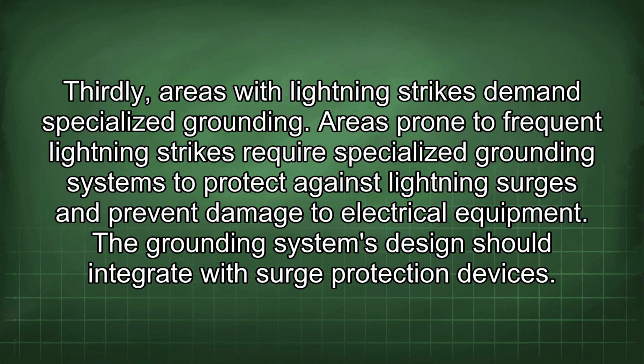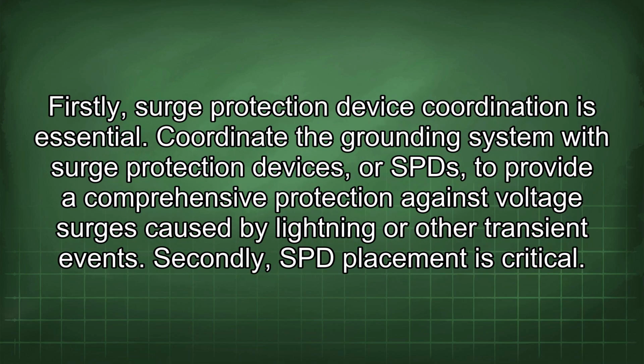Areas prone to frequent lightning strikes require specialized grounding systems to protect against lightning surges and prevent damage to electrical equipment. The grounding system's design should integrate with surge protection devices. Firstly, surge protection device coordination is essential. Coordinate the grounding system with surge protection devices, or SPDs, to provide comprehensive protection against voltage surges caused by lightning or other transient events.